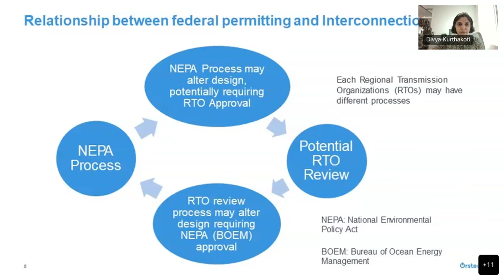Basically, it's an iteration between our design changes and the NEPA process and the RTO or ISO interconnection process here in the US. To look at the interplay between the interconnection process, the design, and the federal process, I've made a high-level block diagram. The input of one process impacts our design, and changes to the design affect the other process. This iteration goes on for quite a significant amount of time.